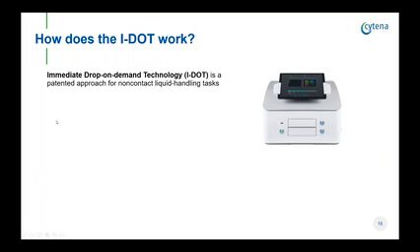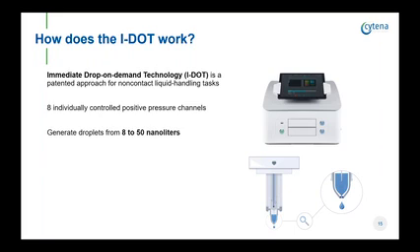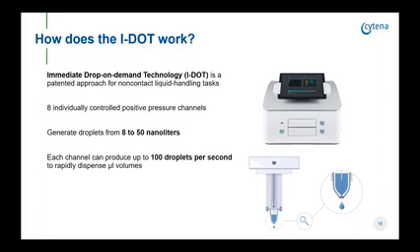Now let me introduce the IDOT, a benchtop instrument for low volume reagent dispensing. The IDOT technology generates droplets using a well-controlled pressure pulse applied to a liquid well with a small hole on the bottom. It comes with 8 individually controlled pressure channels, which can generate droplets with volumes between 8 and 50 nanoliters. Volumes in the microliter range can easily be addressed given that droplets can be generated at frequencies of 100 Hz.